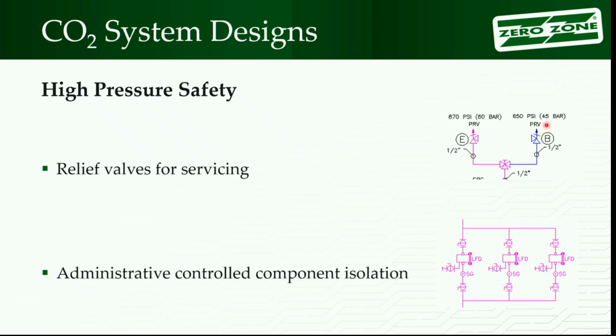I can pump down those liquid lines back into the receiver and I can switch over to a higher pressure safety valve. The reason is that receiver was designed for a higher pressure. And for receivers, higher pressure means thicker walls. That's why everybody doesn't just buy really high pressure receivers, because they get really expensive and they get thick walls. So anyhow, that's a technique to allow more serviceability, less likely to have a release of refrigerant and have to add more back in. You switch back and forth. When using that, it's important that you switch back to the 650 when you're done with your maintenance activity.